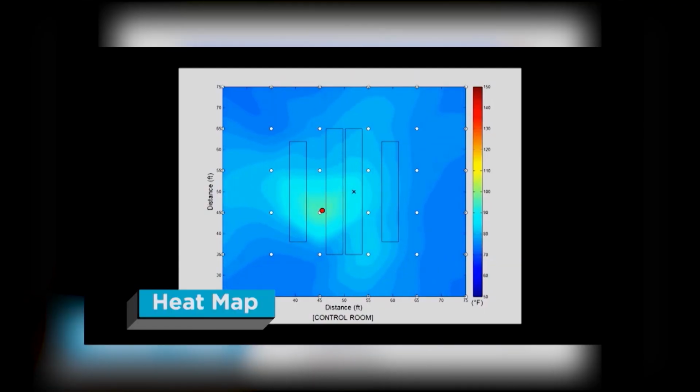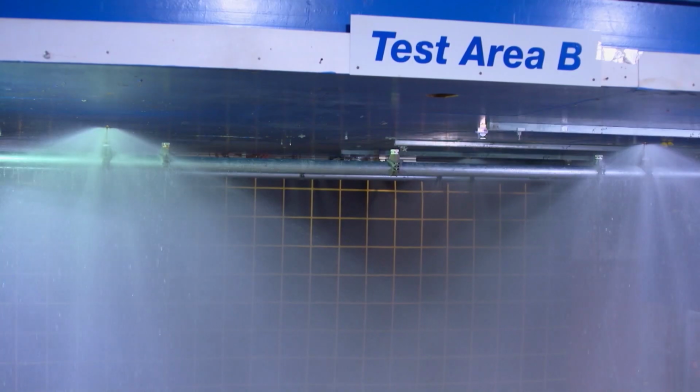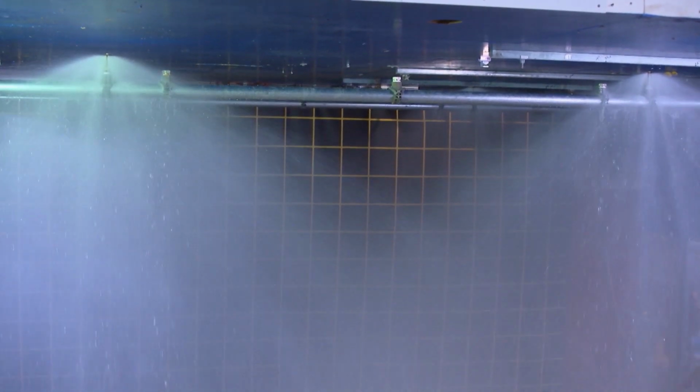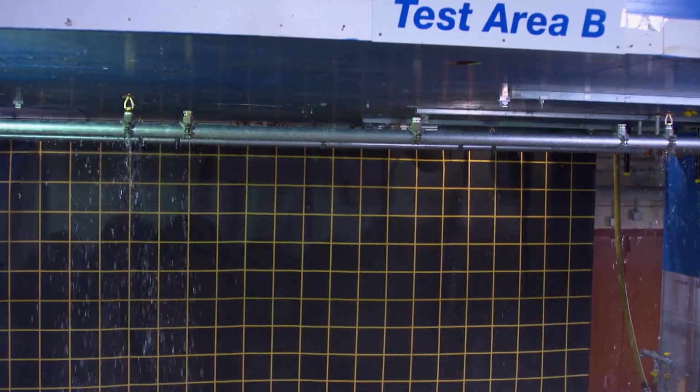These can range from hydrostatic integrity to the strength of the actual frame of the sprinkler to flow distribution or spray distribution, which is actually a test of the spray pattern of the sprinkler for a different application. Can also incorporate multiple full-scale fire tests depending on whatever the hazard we're trying to protect is.